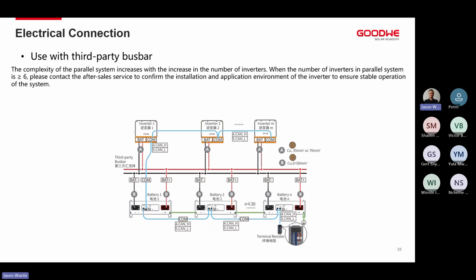Lastly, yes, we can use third-party connections or third-party busbars. We don't necessarily have to use a GoodWe busbar. Please do go through the user manual and confirm the cable layout for this when it comes to communication. Otherwise, you'll be limited to the 160 amps and 8 kilowatts. I've seen it a few times. There is a termination that needs to be done on the actual cable itself, so we need to make sure that we do that. Like I said, I've seen this a few times where we've installed a site, they've used a third-party busbar, and we get stuck at 8 kilowatts on a 12 kilowatt inverter, and we're not sure exactly how to get that resolved. It comes down to battery communication. So just make sure that we have the terminations done correctly, and the cable comms done correctly on the batteries.